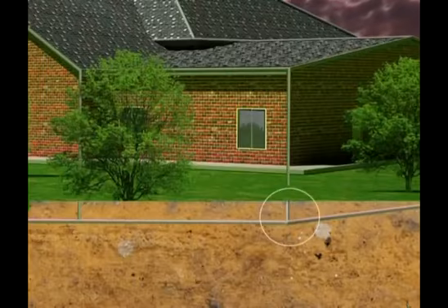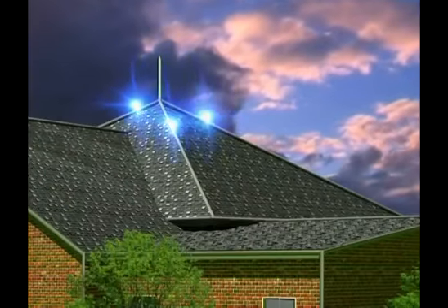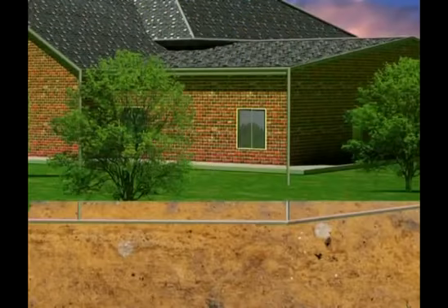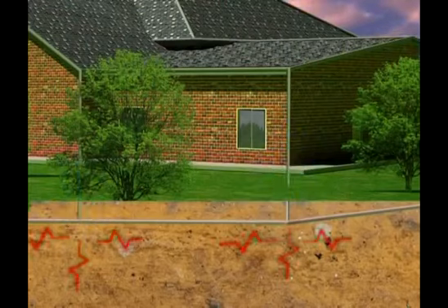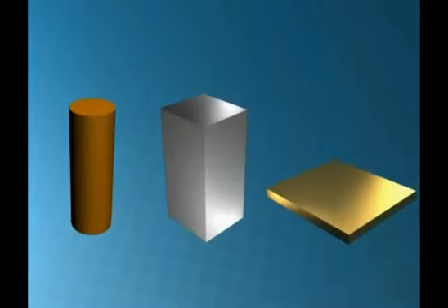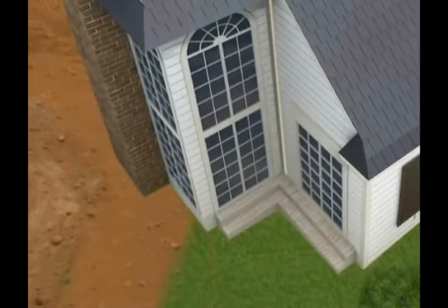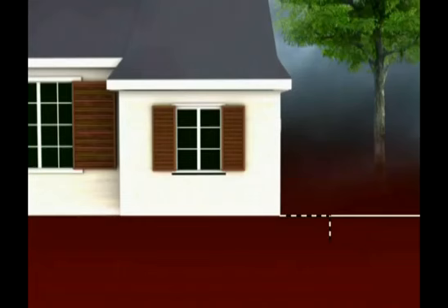The earthing system is the third component in the external protection system. The earthing system carries the electricity captured by the air terminal and conveyed by the down conductor to the earth. GI metal sheets or copper wires are used for preparing the earthing system. The earthing system thus prepared is placed at a distance of 1 meter from the periphery of the building and at a depth of ½ meter.